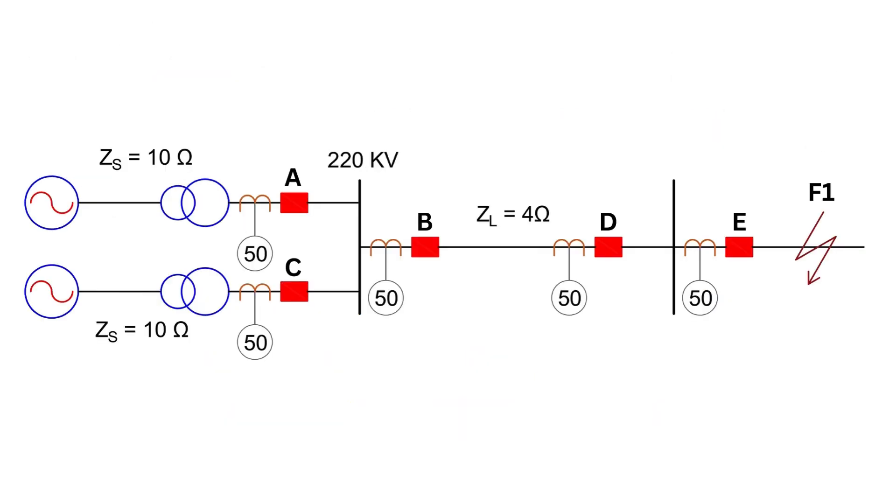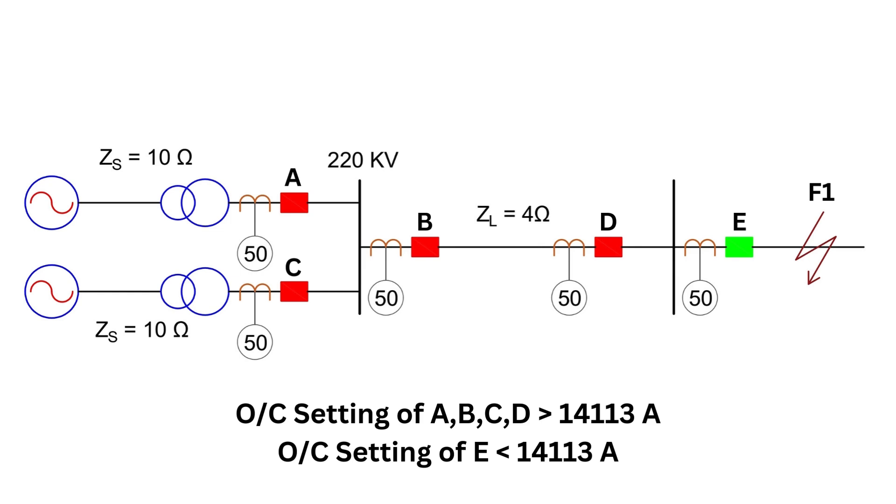To isolate this fault, only the breaker at point E should trip while keeping the rest of the system energized. In power systems, the goal is to isolate only the faulty section without disturbing healthy sections. Therefore, the setting of the overcurrent relay for the other breakers should be higher than 14,113 amperes, while the setting of the overcurrent relay for breaker E should be lower than this value to ensure that only breaker E trips for this fault.